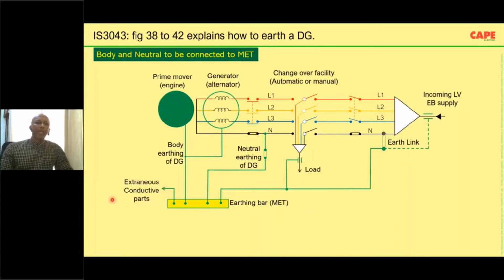And now this bus bar is connected to extraneous conductive parts. Extraneous conductive parts means the metallic parts in a building, such as air conditioner ducts, metallic fire pipes, the metal reinforcements, and so on. Then the bar is also connected to an independent earth electrode. Of course, don't get carried away by the words independent earth electrode, because the earthing here, this symbol, is called chassis earthing.